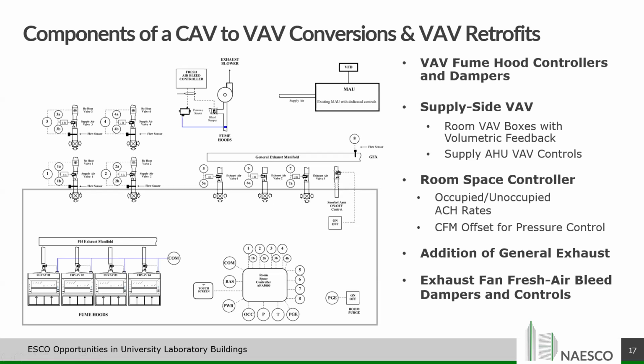Now, if it was an existing VAV system and you're just retrofitting it, all these valves are going to be here already. So it's just a matter of retrofitting them with new fast-acting electronic actuators and controlling them to your lower air change per hour rates when the sash is closed. And this is making sure that your face velocities are where they need to be. Every lab is going to have some general exhaust as well.